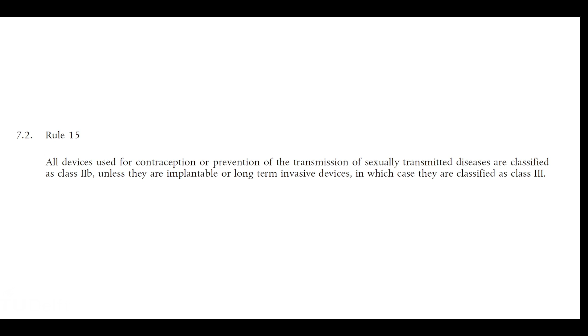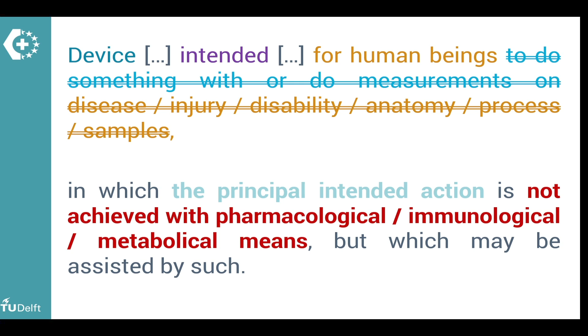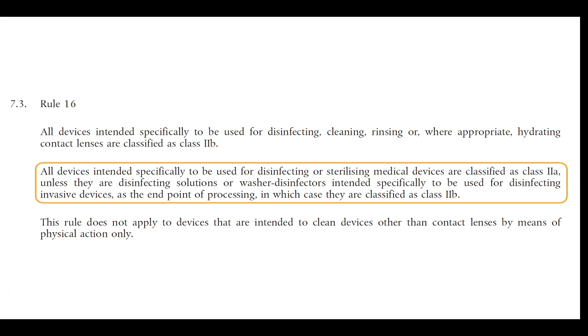This rule exists because, for example, strictly speaking, contraception does not fall within the standard definition of a medical device. Because of Rule 15, condoms are Class 2B devices and intrauterine contraceptive devices are even Class 3. And another interesting example is Rule 16, which is about devices used for cleaning, rinsing, disinfecting, or sterilizing other medical devices. Because of this rule, your contact lens disinfection fluid is considered a Class 2B device. That's because according to the definitions in the MDR, contact lenses are invasive devices, since the surface of the eyeball is considered a body orifice.